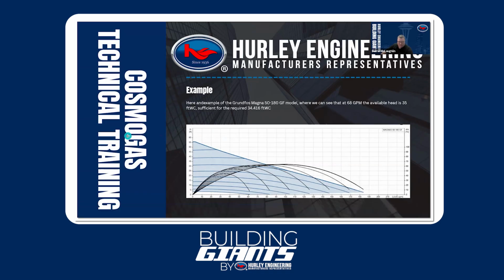Mike, can you think of anything that you would like to add to this? Yeah, it's pretty critical with pumps and flows, especially when you're applying a lot of heat to a small amount of water in that heat exchanger. You can always precipitate out those minerals that are hardness in the water. So getting that correct is going to make that piece of equipment not be a 3 to 5 year piece of equipment. It's going to last 15 to 20 years if you're keeping that flow where it should be. So that's a pretty critical point.